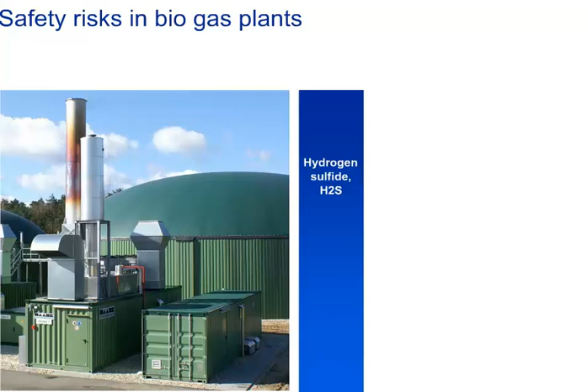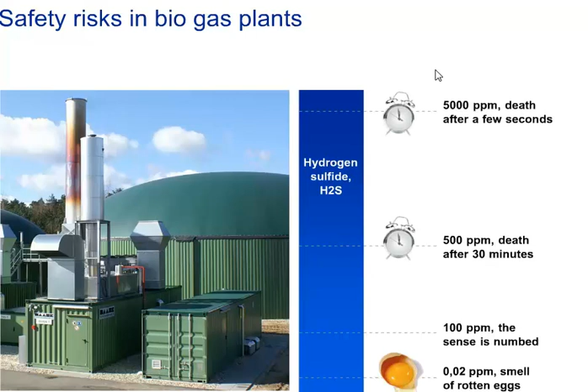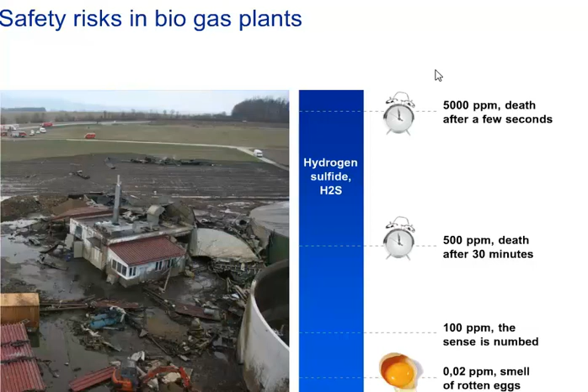In biogas plants, we are faced with a combination of risks from hydrogen sulfide, which constitutes a serious toxic hazard. At a level of just 0.02 ppm, we notice the typical smell of rotten eggs. More than 100 ppm of hydrogen sulfide cannot be detected because our sense of smell would be numbed. So we're not able to detect extremely high concentrations, which are life-threatening, in 30 minutes at 500 ppm, or in a few seconds at 5,000 ppm concentration. Methane can also create explosive atmospheres, whereas carbon dioxide and nitrogen are harmful as they are a choking hazard.